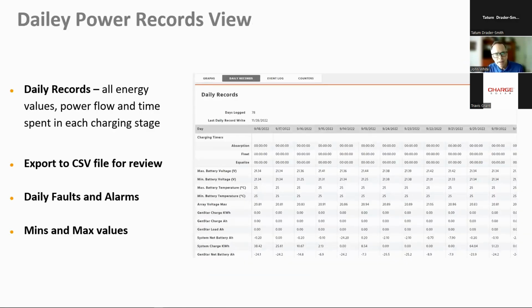The daily power records view is another really neat feature. It gives you graphs of what's taken place, event logs, and counters that can be reset. The daily records pick up all the information, date stamp it, time stamp it, and you can export this as a CSV file for review. It gives clear indications of daily faults or alarms, along with minimum and maximum values of all the different criteria, which is quite a long list.